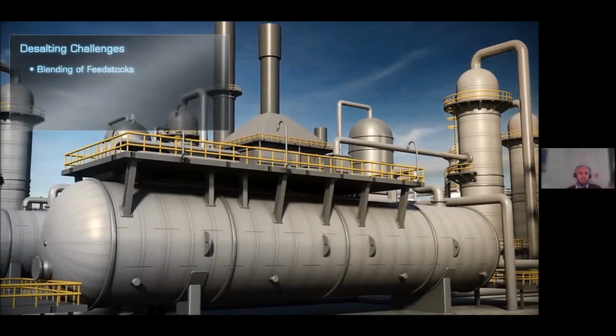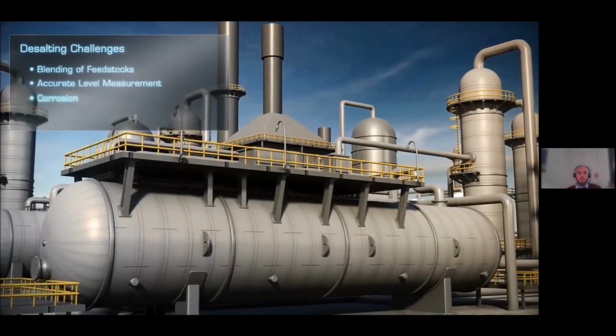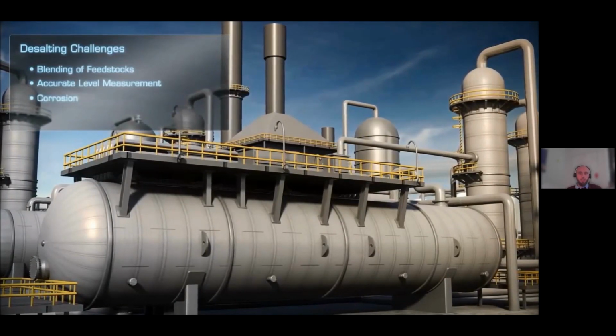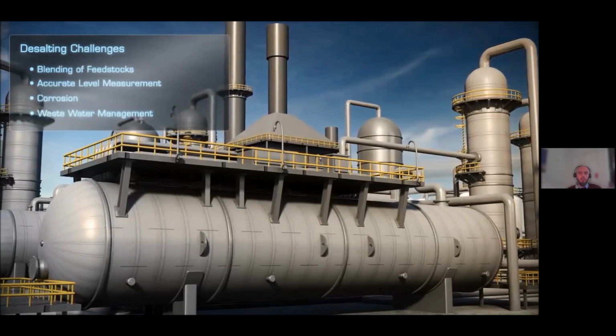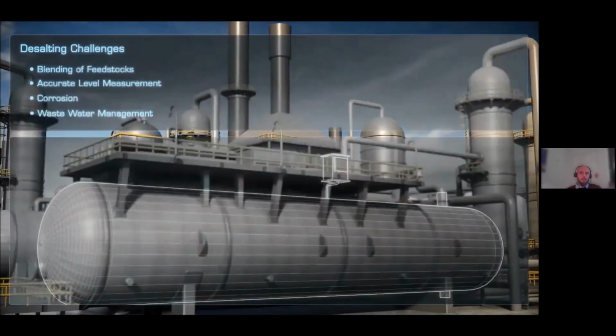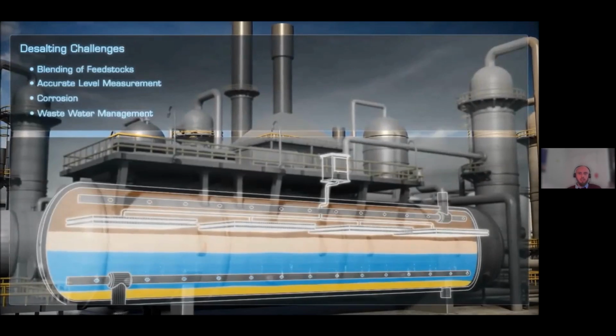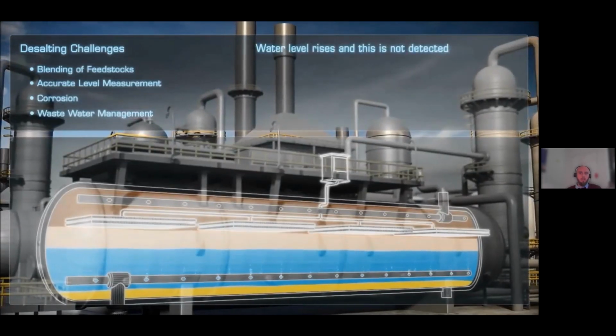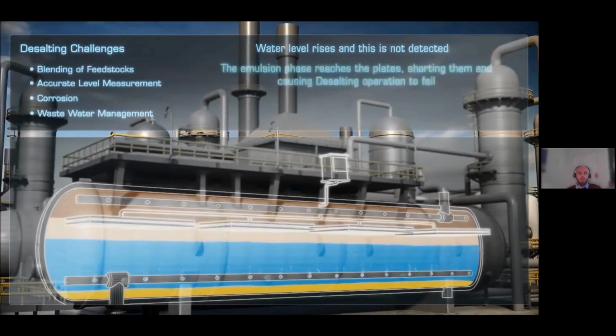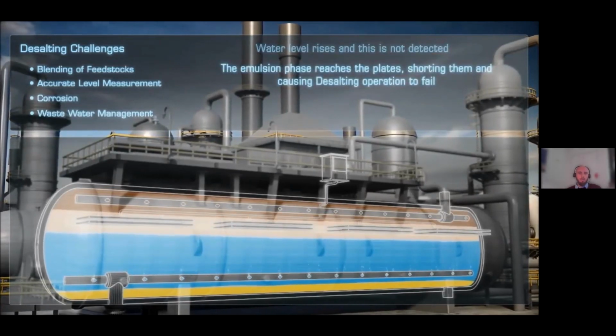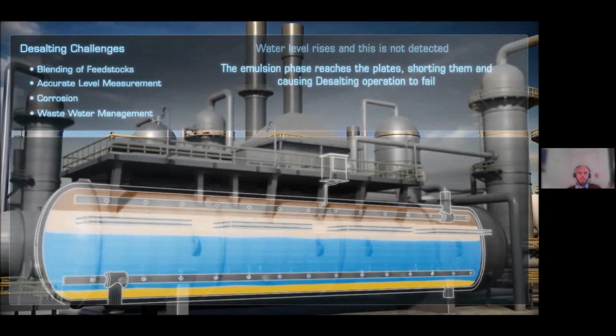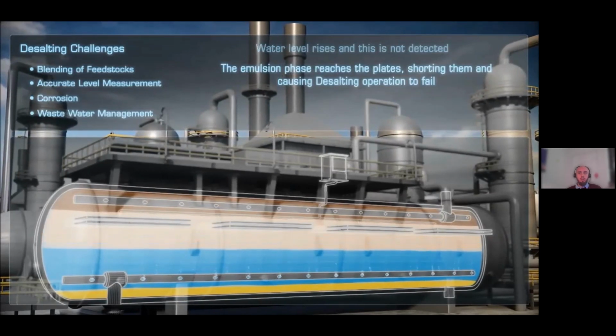So some of the challenges in this include the blending of feedstocks, accurate level measurement, corrosion, and wastewater management. When the water level rises and it's not detected, the emulsion phase might reach the plates, shorting them, and cause the desalting operation to fail. Tracerco's high temperature profiler would provide live monitoring and process control, preventing this from happening.